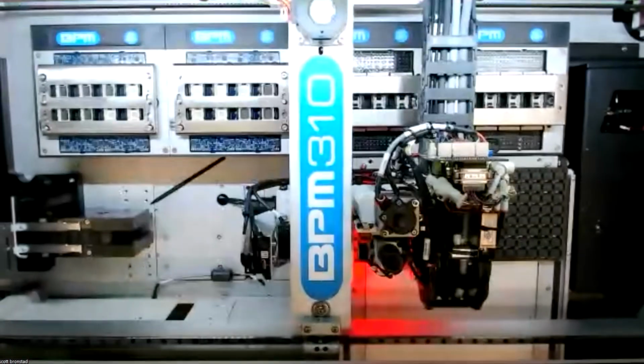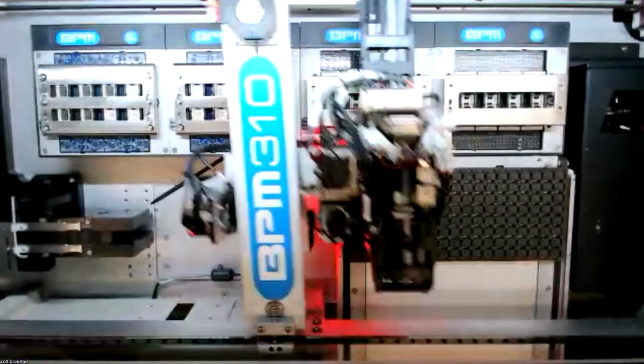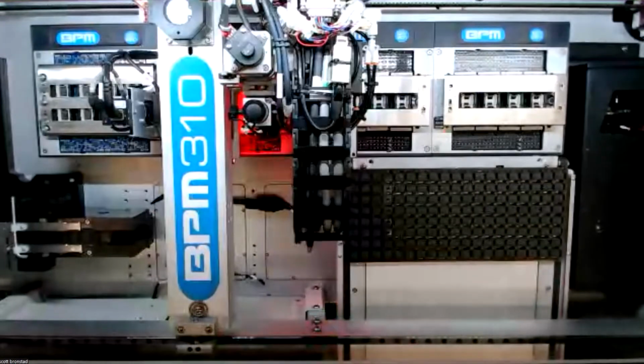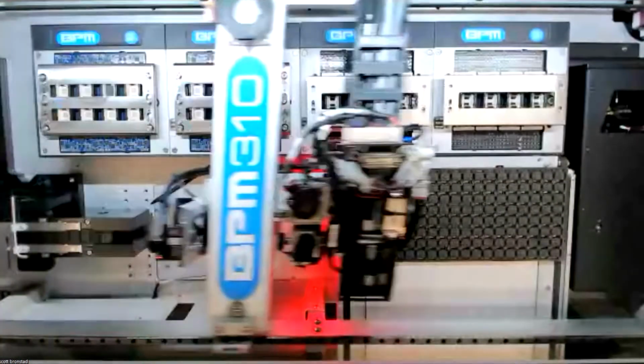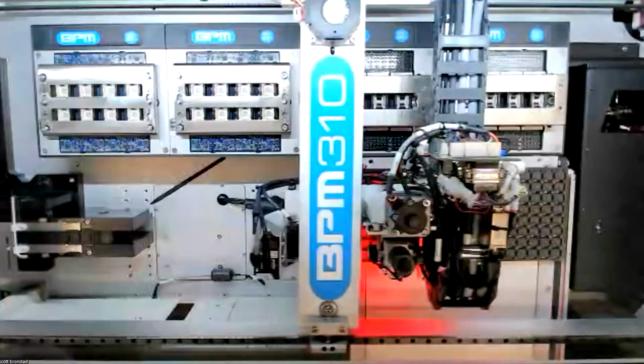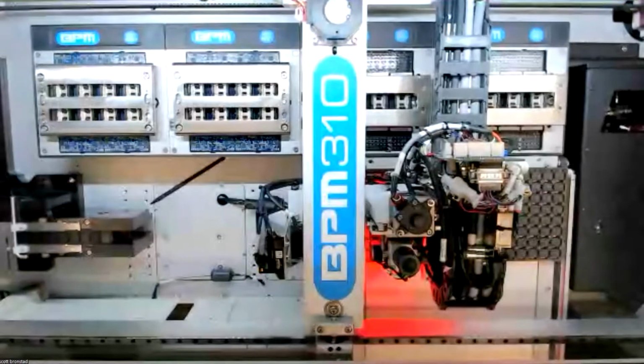And we also have an odometer on each of the sockets too, right? With the socket module counter, that allows customers to become familiar with the replacement rates. And then they preset that and do a cleaning routine first, and then a socket maintenance routine interval, is what we call that.